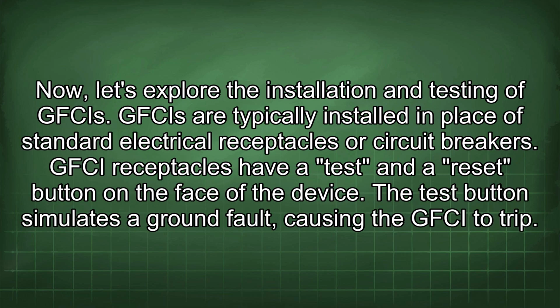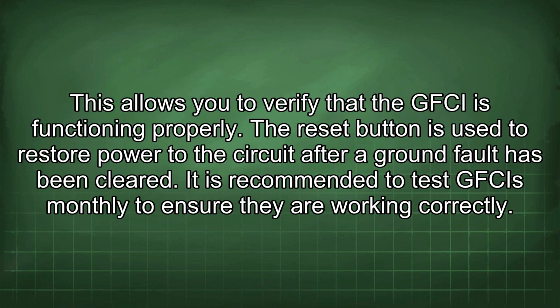Now let's explore the installation and testing of GFCIs. GFCIs are typically installed in place of standard electrical receptacles or circuit breakers. GFCI receptacles have a test and a reset button on the face of the device. The test button simulates a ground fault, causing the GFCI to trip. This allows you to verify that the GFCI is functioning properly. The reset button is used to restore power to the circuit after a ground fault has been cleared.